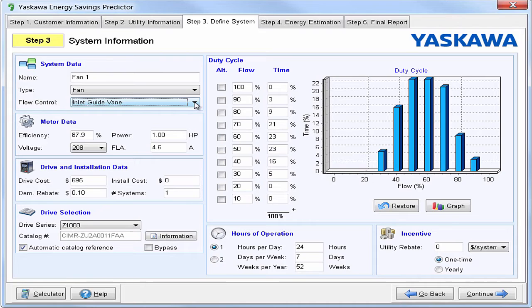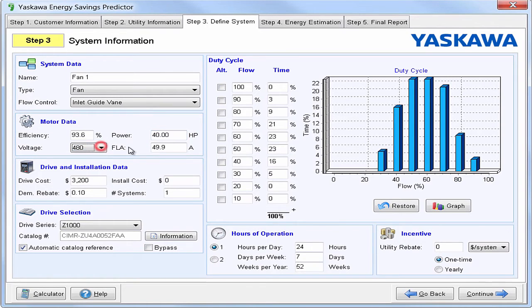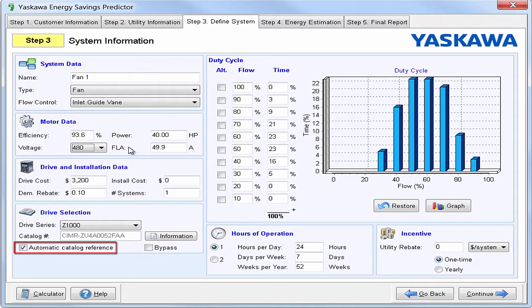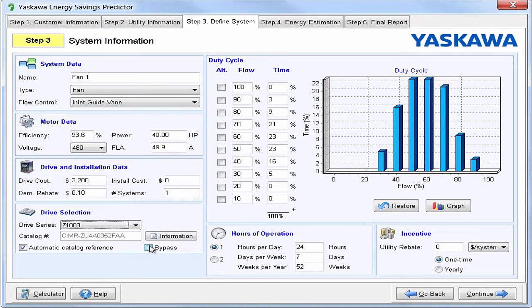Note that once the new system is installed, this can either be locked open or removed, because now the VFD will be able to vary the flow. Next, we'll just need to input some motor data. For our example, we're going to be using a 40 horsepower motor and a voltage of 480. You can adjust your full load amps and efficiency if need be. The software has chosen an appropriate drive system for our application, but this can be adjusted manually. The user can choose between the Z1000 and the Z1000U matrix drive, and option the system for a bypass if it calls for it. You can add install costs to give you an even more accurate payback period.